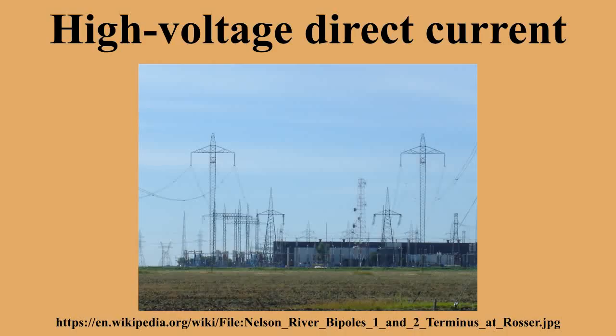A long-distance point-to-point HVDC transmission scheme generally has lower overall investment cost and lower losses than an equivalent AC transmission scheme. HVDC conversion equipment at the terminal stations is costly, but the total DC transmission line costs over long distances are lower than AC line of the same distance. HVDC requires less conductor per unit distance than an AC line, as there is no need to support 3 phases and there is no skin effect.